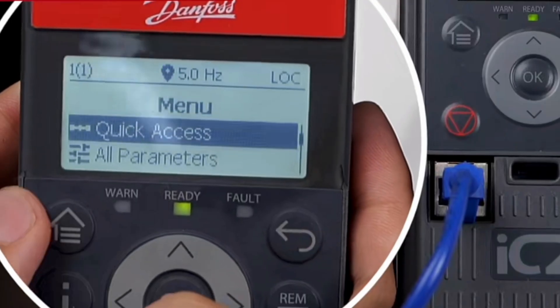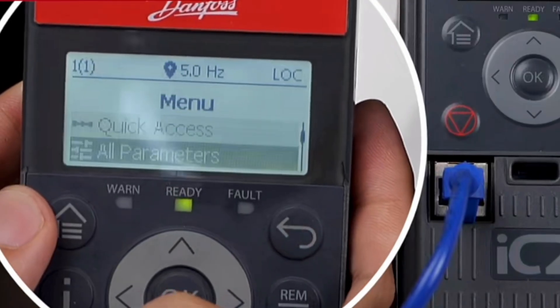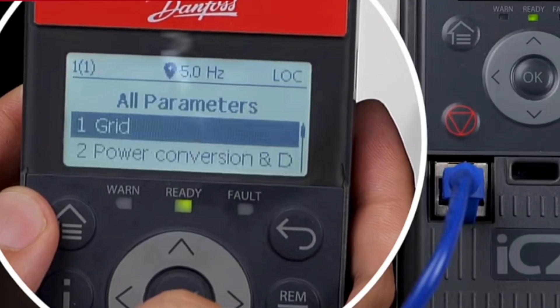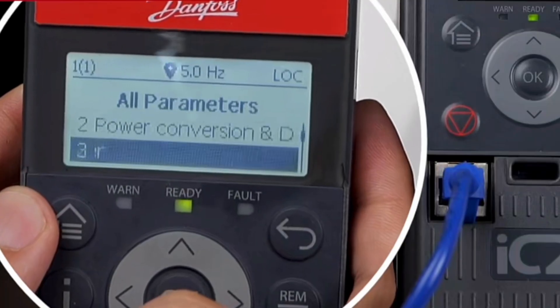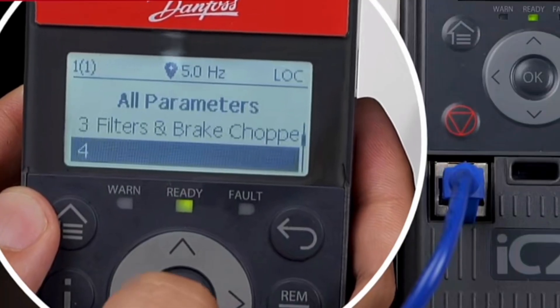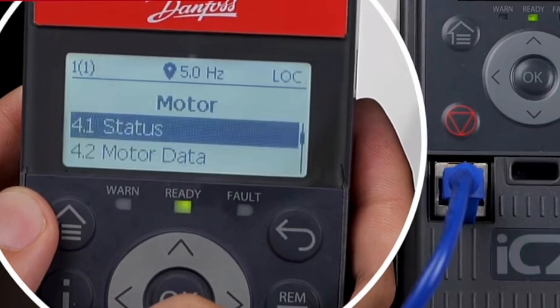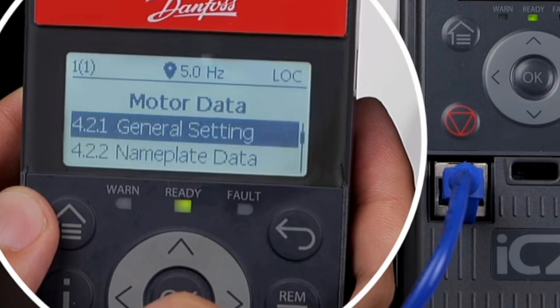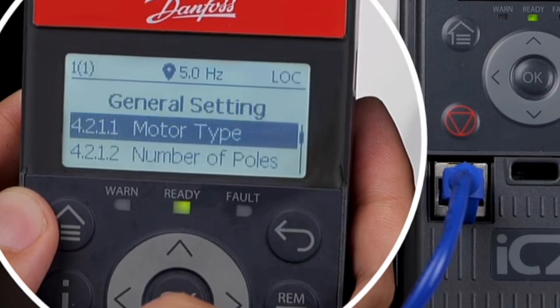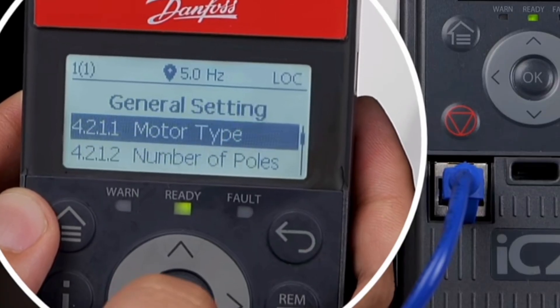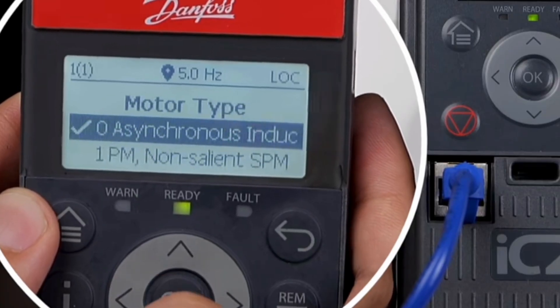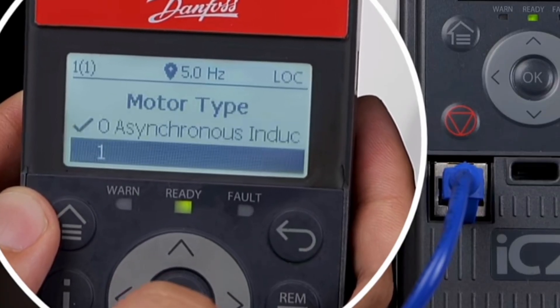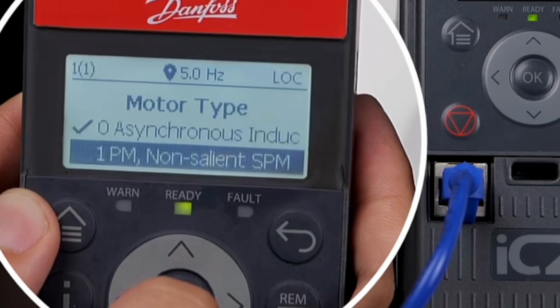If using a permanent magnet synchronous motor, open the fourth parameter group in the menu to set the motor parameters. Set parameter 4211 to select the motor type as 1, SPM motor.